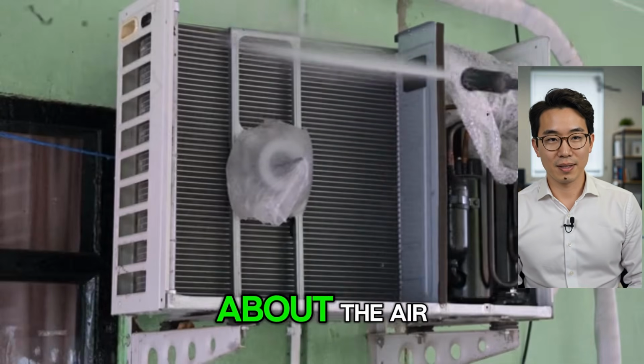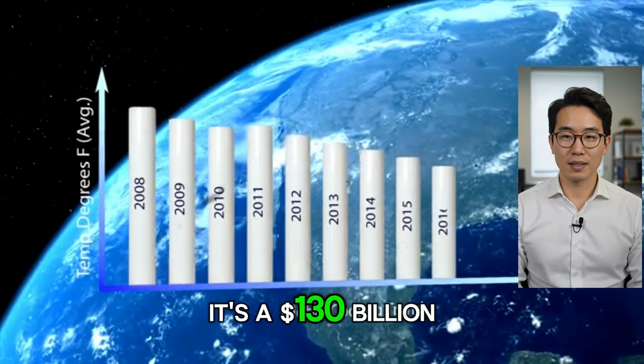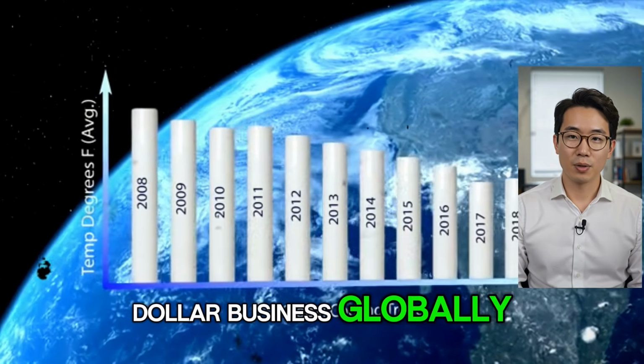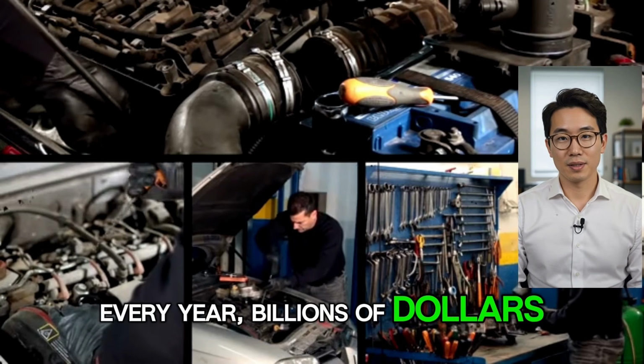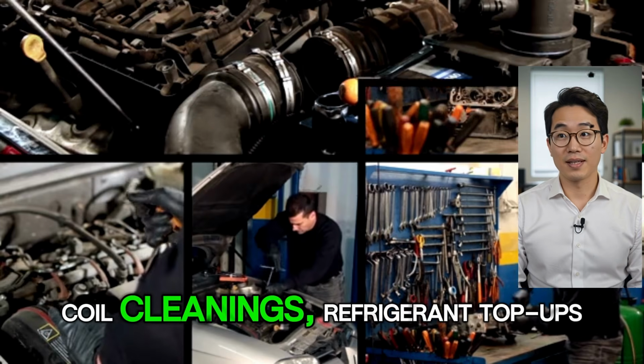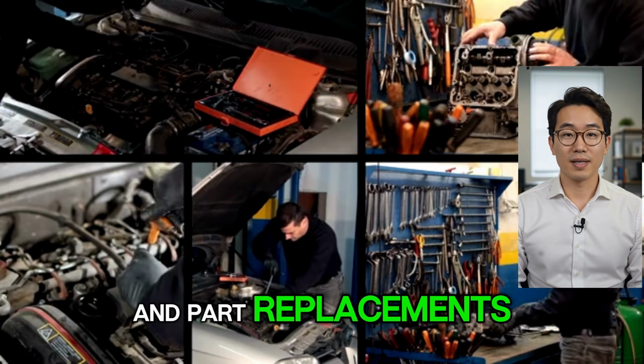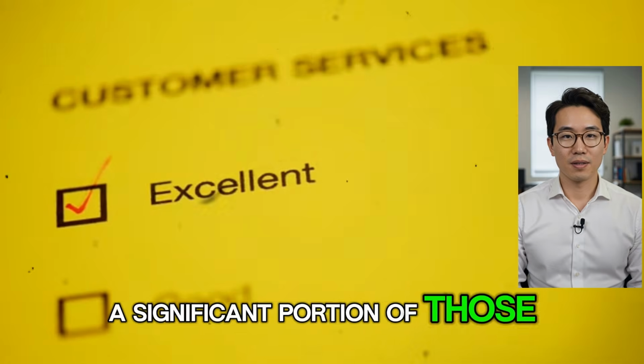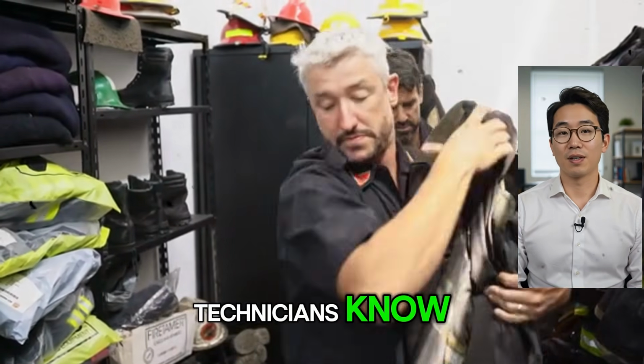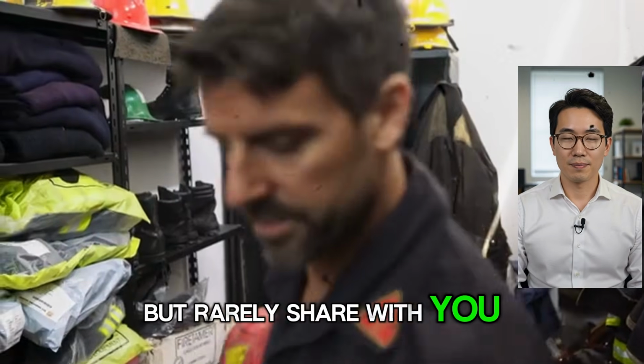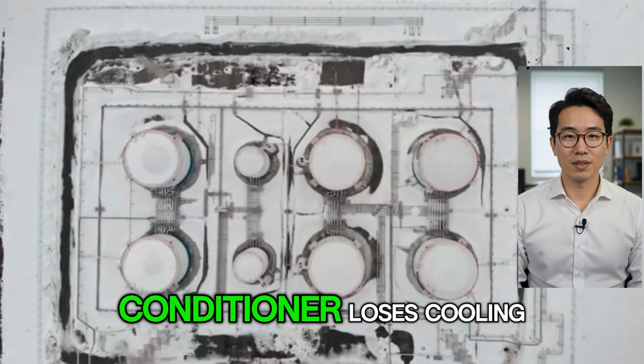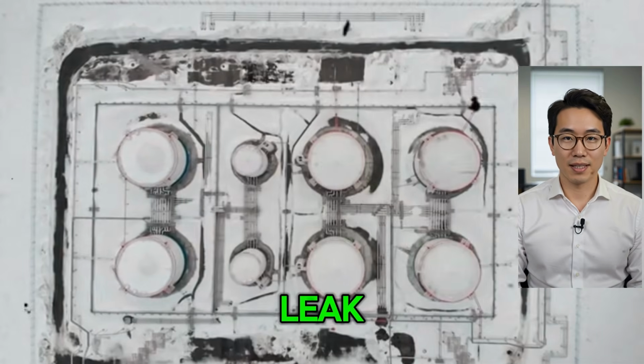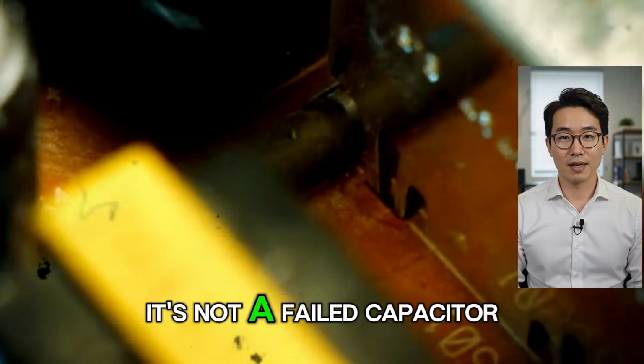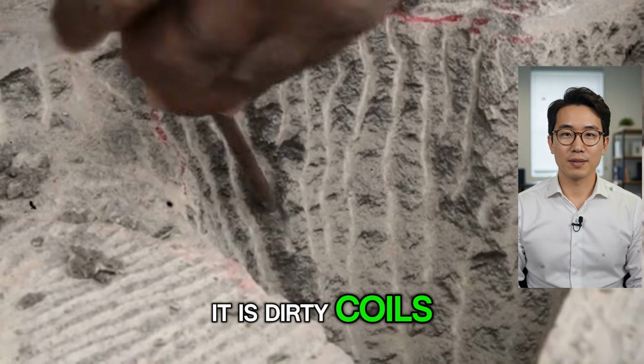Let me tell you something about the air conditioning industry. It's a $130 billion business globally. Every year, billions of dollars are made from service calls, coil cleanings, refrigerant top-ups, and part replacements. A significant portion of those service calls, they don't need to happen. Here's the truth that HVAC technicians know, but rarely share with you. The number one reason your air conditioner loses cooling power is not a refrigerant leak, it's not a broken compressor, it's not a failed capacitor, it is dirty coils.